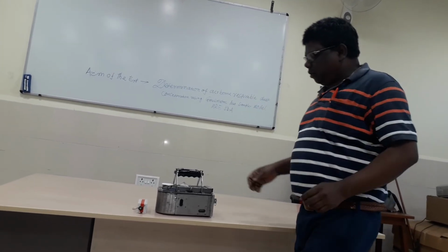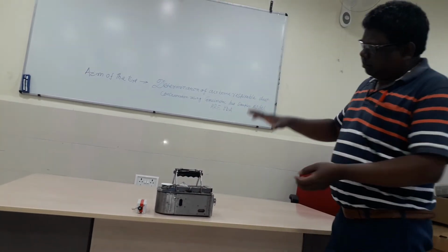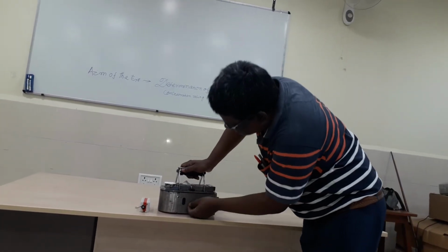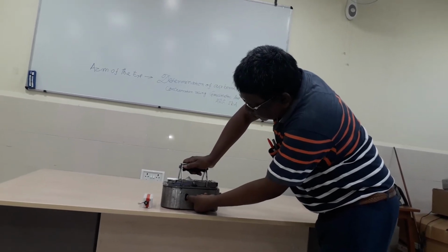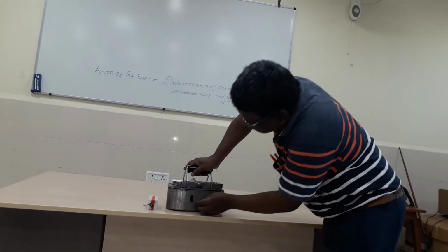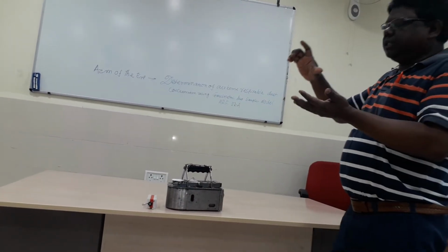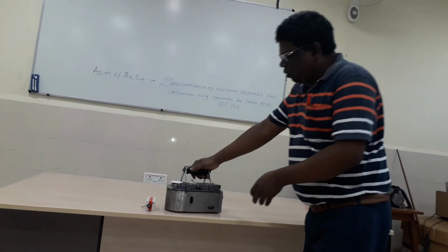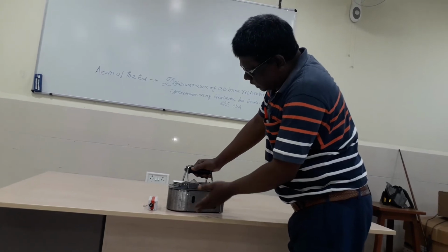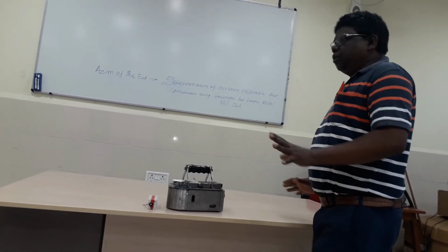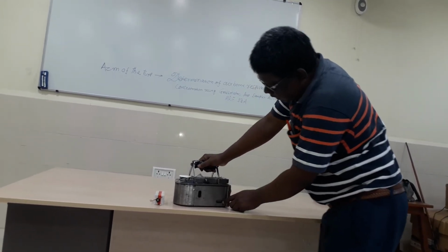It is designed such that this bubble will jump. One bubble you can see jumping here. The lower limit is 2.4, the middle is 2.5, and the upper is 2.6. The bubble will jump between 2.4 and 2.6, which means the average flow is 2.5 liters per minute.